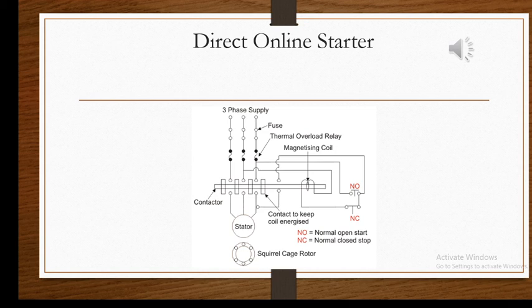The benefits of direct online starters are it's simple, it's economical, it's suitable for small motors, and it's easy to operate, while the disadvantages are it's mechanically tough, it still consumes high starting current, and it causes a dip in the voltage, so it's not suitable for motors with high voltages.